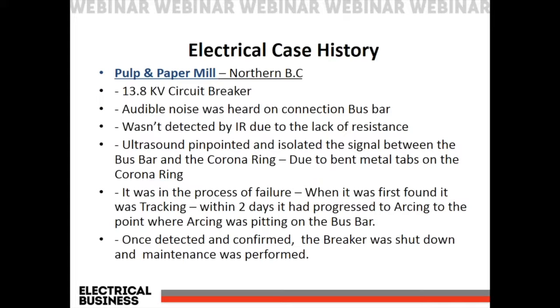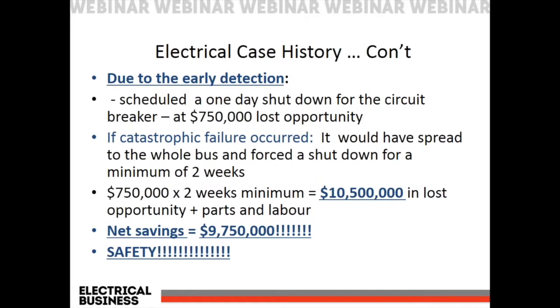And so when they detected it, they shut it down right away. And when they did that, there were some big benefits. Number one, no one was hurt. And we're going to talk about safety more than anything else. No one was hurt in this particular case study, and they were down only for 1 day at a loss of $750,000 for that day. But what they noted to me was, if it had gone catastrophic in that circuit breaker, there would have been a lot more issues happening, and they would have been down for approximately 2 weeks at $750,000 a day.